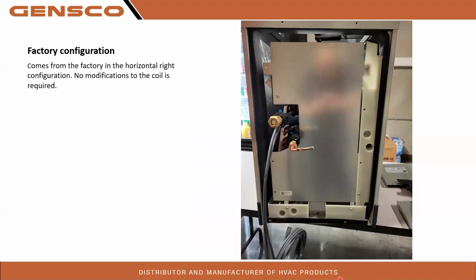Factory configuration. I know this is sitting up, but this is actually a horizontal right configuration. This comes from the factory as a horizontal right. So out of the box, if you're installing this horizontal right, there is nothing you need to change. It is ready to go. You don't need to pull the doors off, don't need to pull the coil out, anything. Just go ahead and put it in there and get that thing installed.